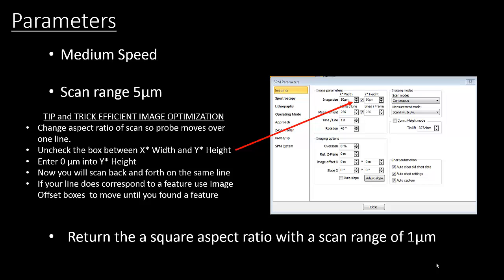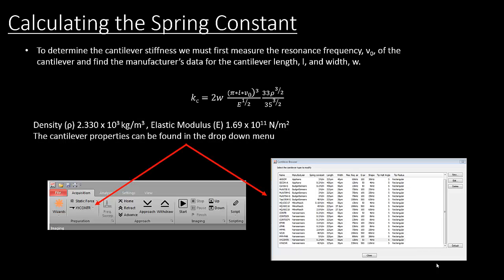If your line does not correspond to a feature, use the offset boxes to move until you find one. After you're happy with your optimization choice, return to a square aspect ratio of a scan range of about 1 micron. Part 3. Determine the spring constant. To determine the cantilever stiffness, we first must measure the resonance frequency of the cantilever and find the manufacturer's information for its length and width.